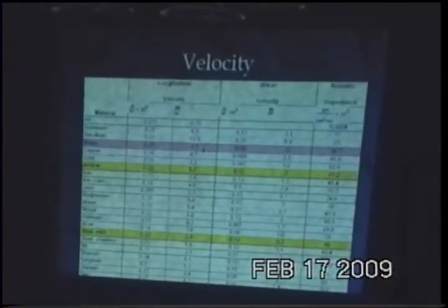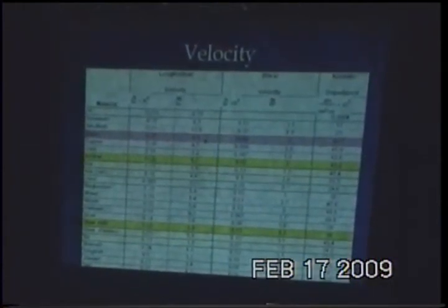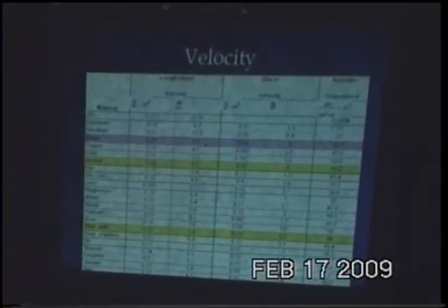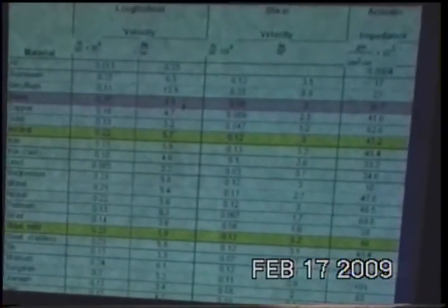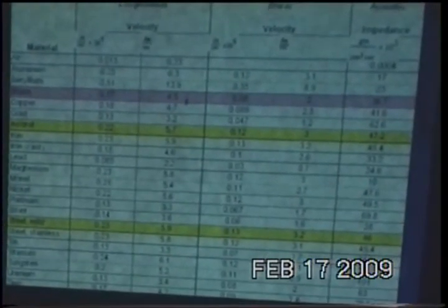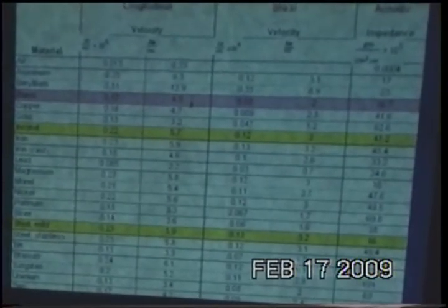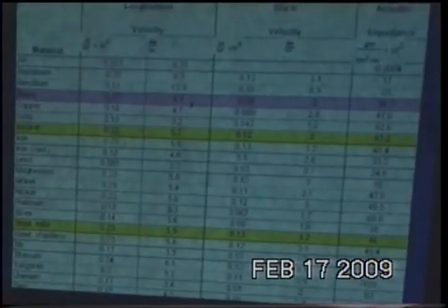The velocity of the material matters, and velocity differences between materials are significant. As a general rule, if you pick up a shoe for an angle beam test, it's probably a shear wave shoe made for carbon steel, depending on what shop you're in. But if you use a carbon steel angle beam shoe on an austenitic material, like Inconel or stainless, your actual refracted angle will be off by about 2 degrees.